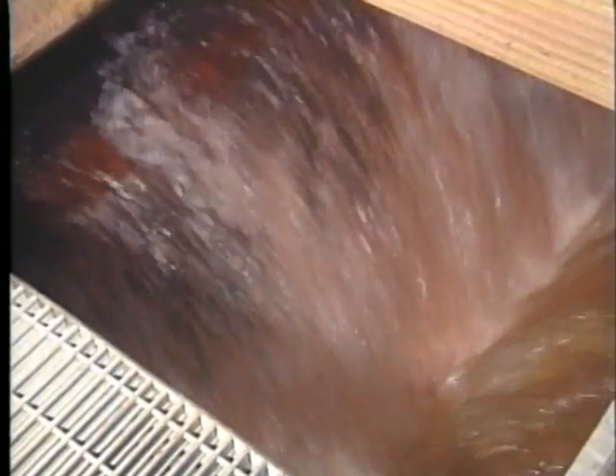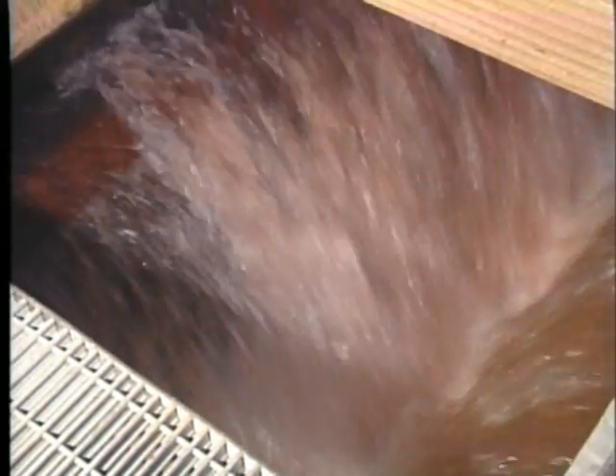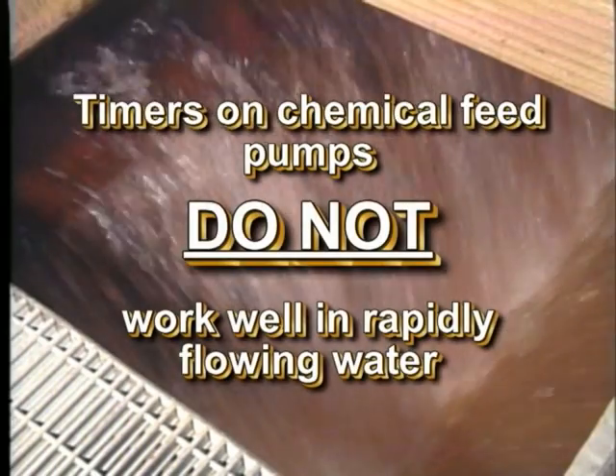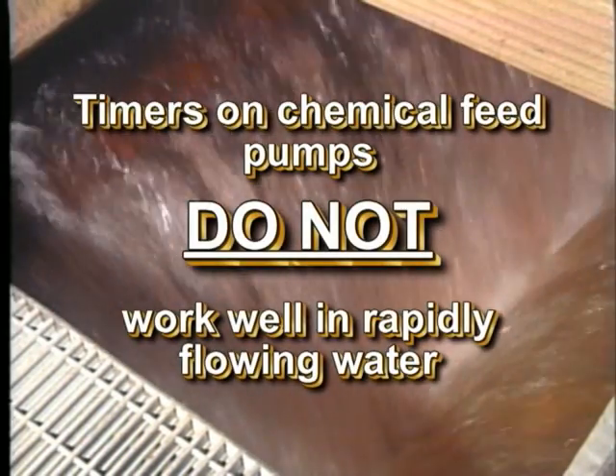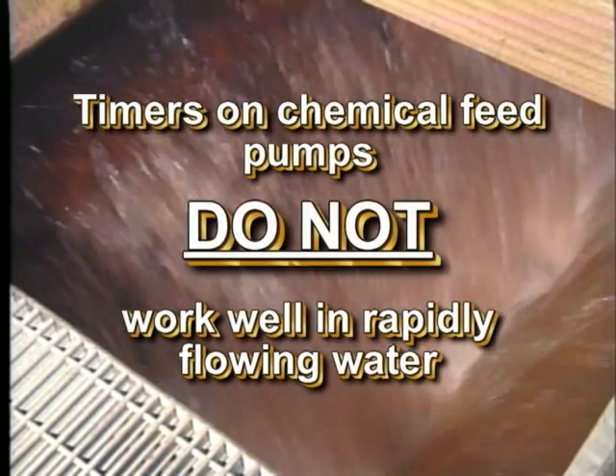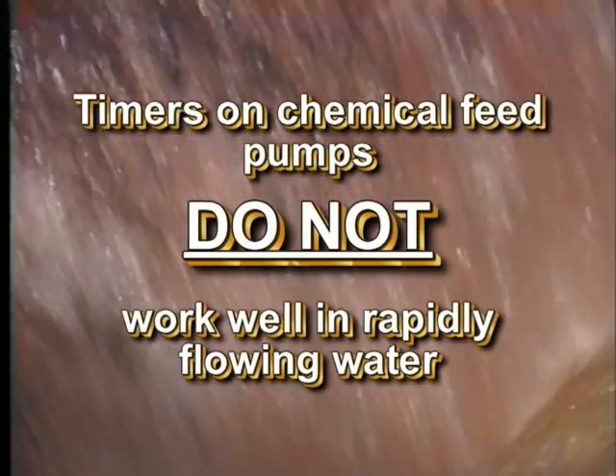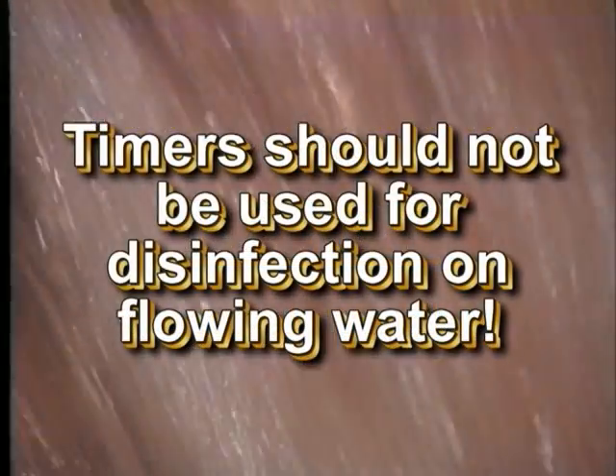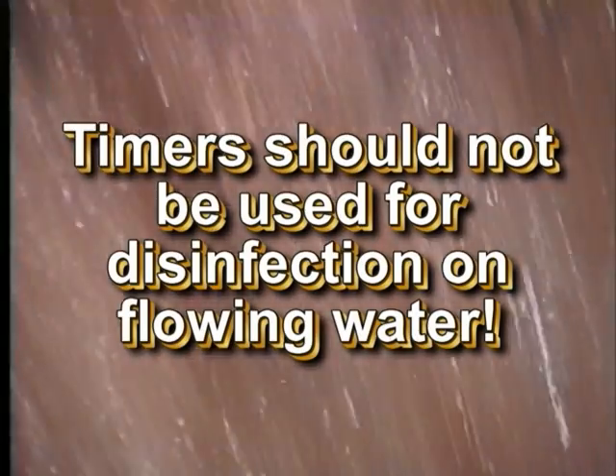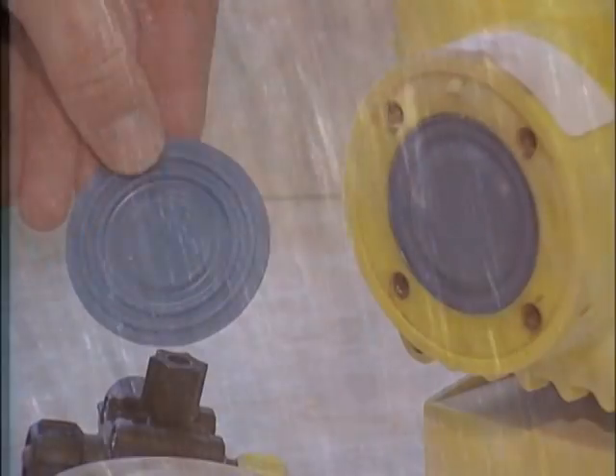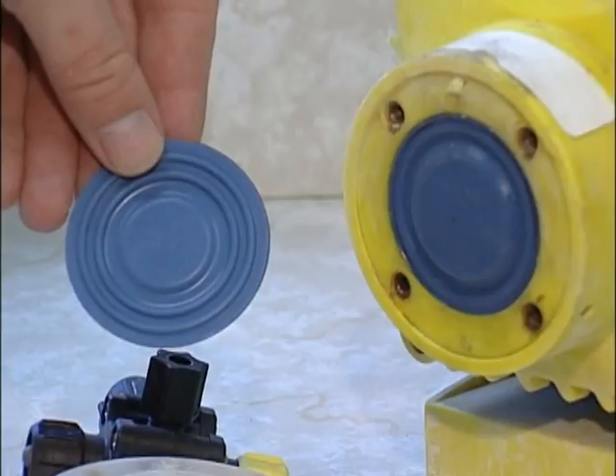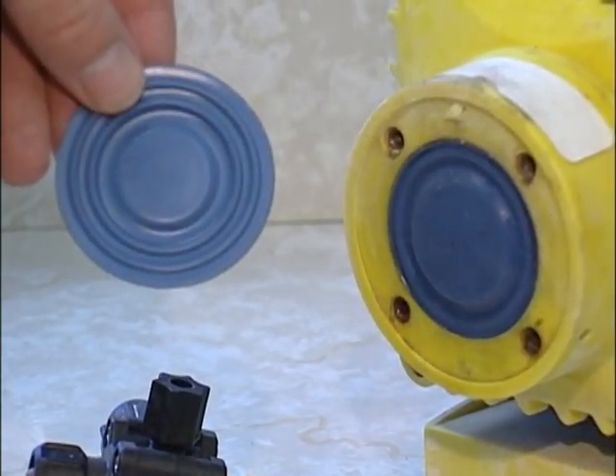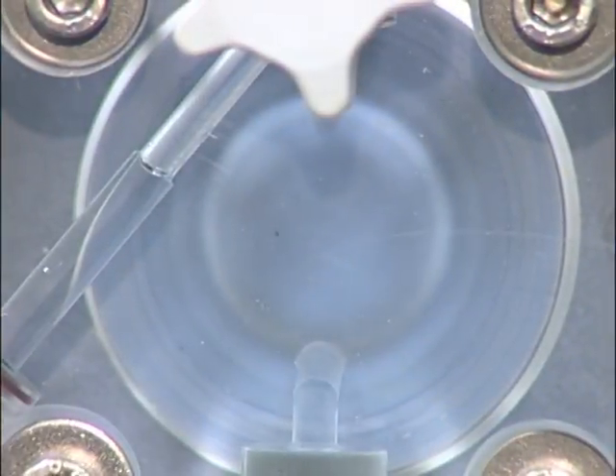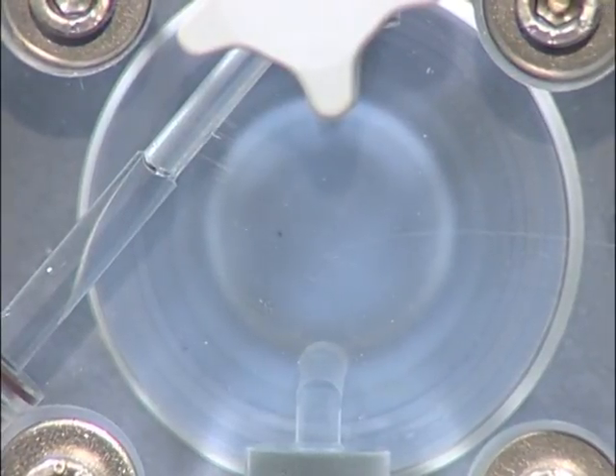This application is suitable for situations where the chemical is not applied to rapidly flowing water. For example, having off cycles where there is no chemical being added for a length of time while the raw water is still flowing would not be appropriate for a disinfection application. The diaphragm pumps use a flexible diaphragm to inject the liquid. The diaphragm simultaneously draws the chemical into the chamber and pushes it out the top into the feed line with every cycle.